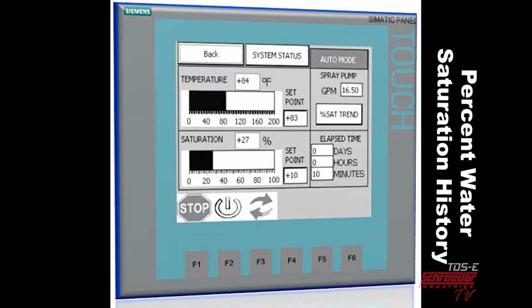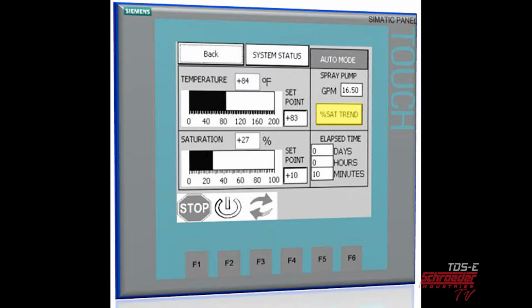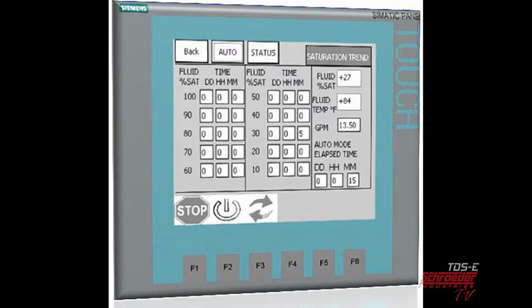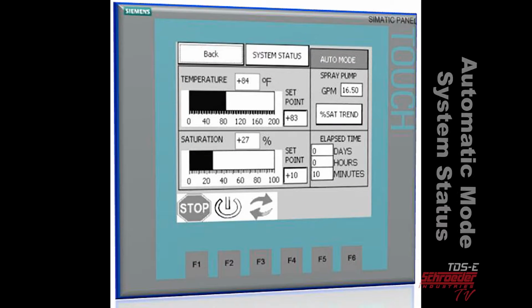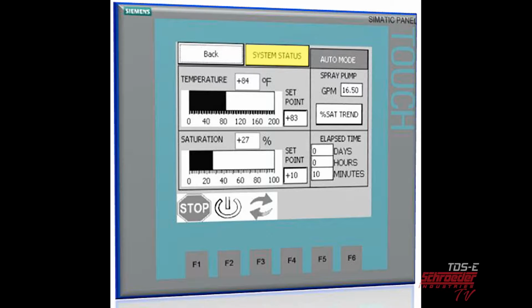The percent water saturation history screen can be accessed by pressing the percent saturation trend button in the auto mode screen or the percent button in the system status screen. This is a read-only screen and will record how long it took the current cycle and percent water saturation to reach 10 benchmarks, 10% through 100% in 10% increments. The running timestamps are retained until a new auto mode cycle is started. To start a new auto cycle mode, simply press the hard key F2, even if the power is lost. The system will not record the values during a short interval at startup to allow the system to complete flush, therefore preventing false readings.